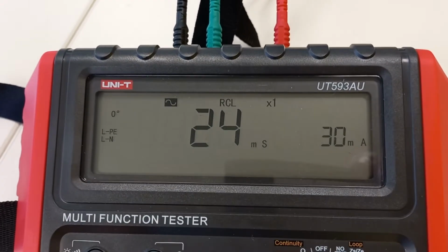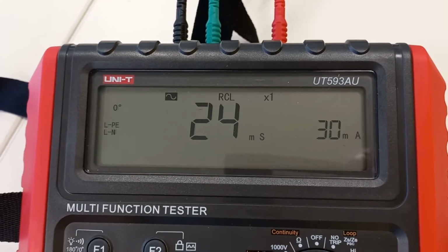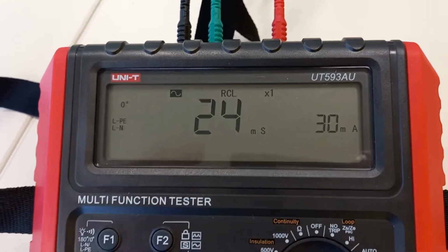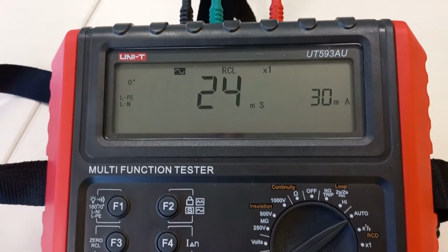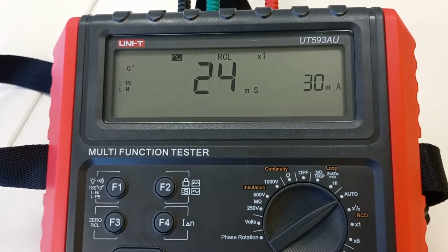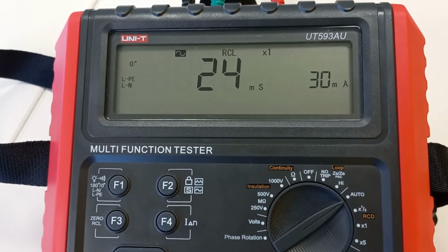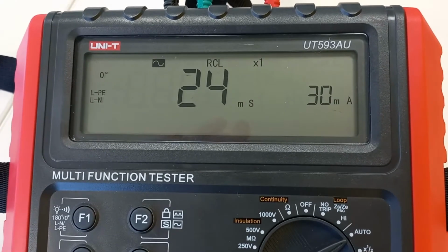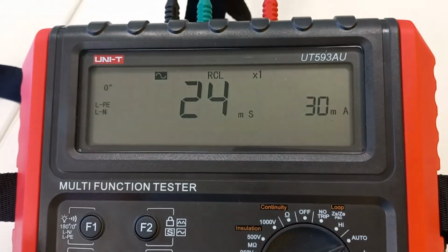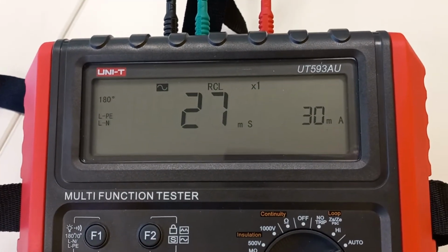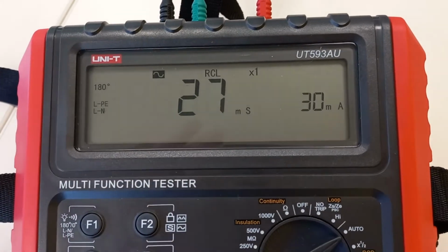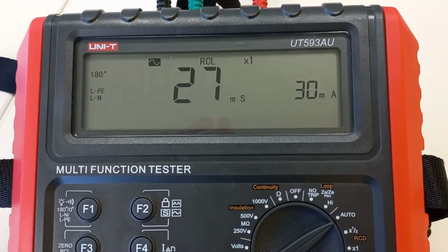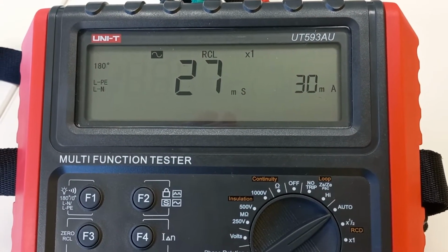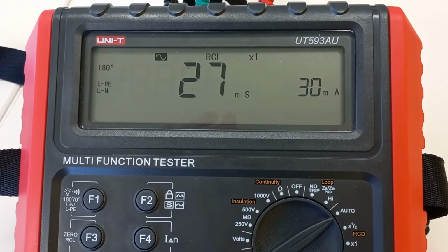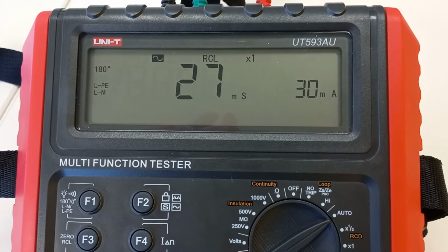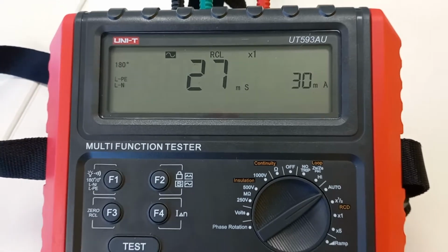At ×1, at 0 degrees starting, it tripped at 24 milliseconds. This, by regulation, has to trip within 300 milliseconds, and it tripped at 24 milliseconds, so that's good. At 180, though, it tripped at 27 milliseconds. We take the longest time as the actual record. So we put down 27 milliseconds at ×1, which is well within the 300 milliseconds that we are permitted to have.